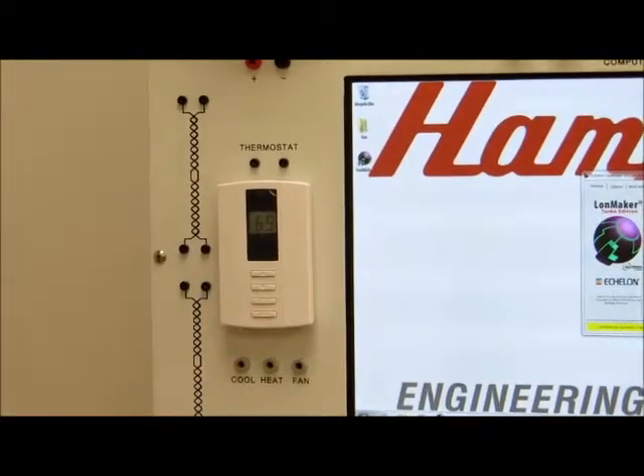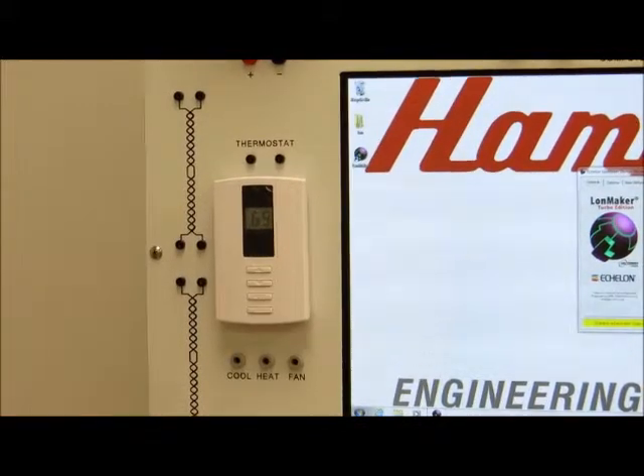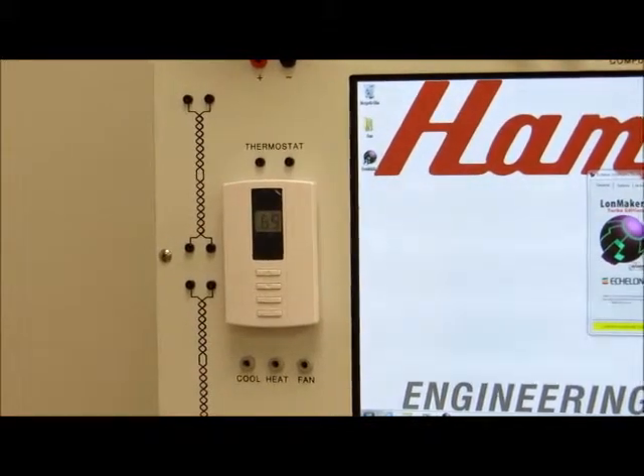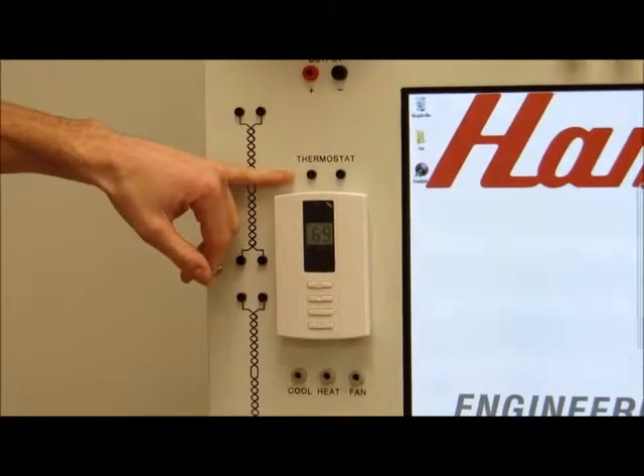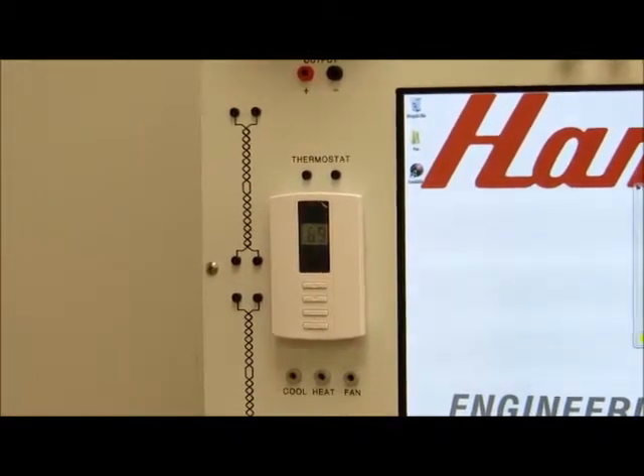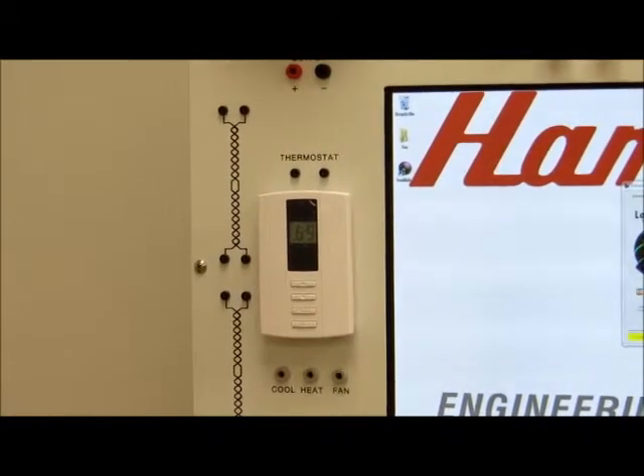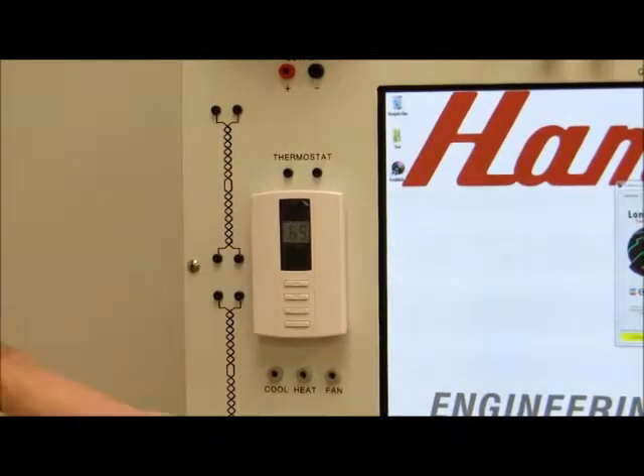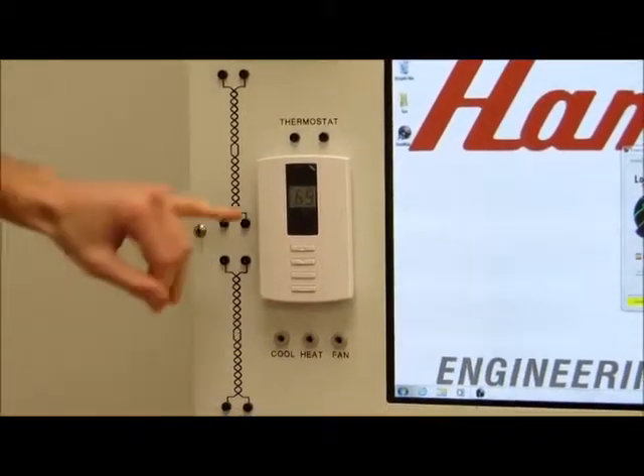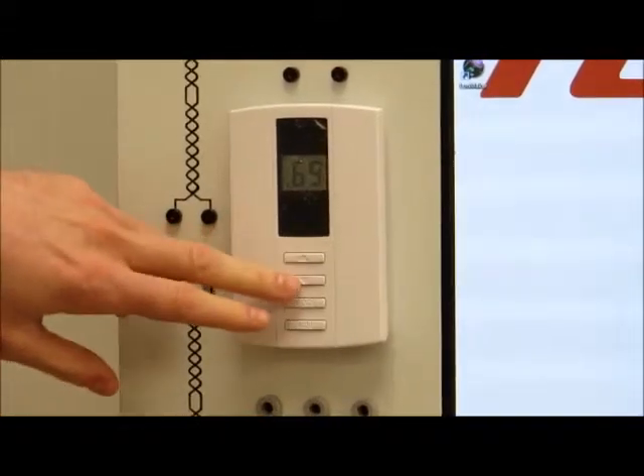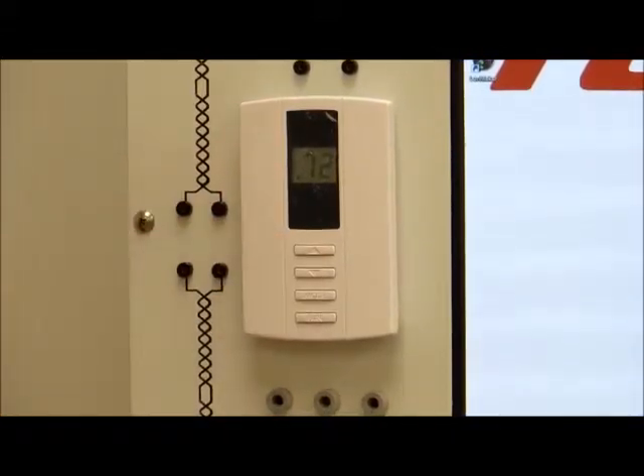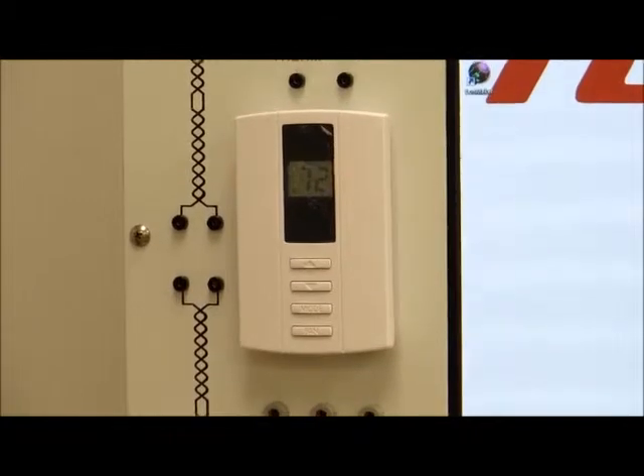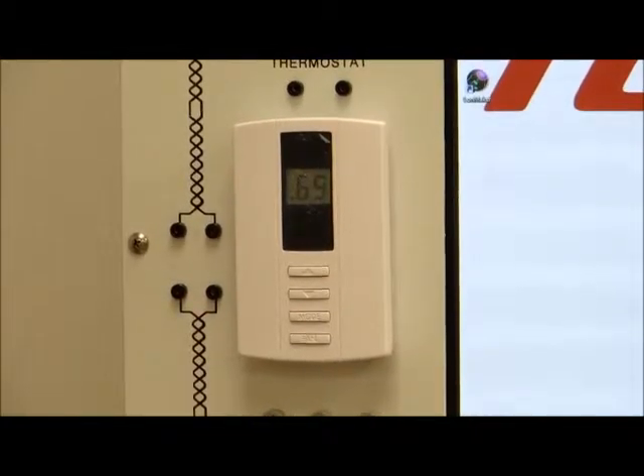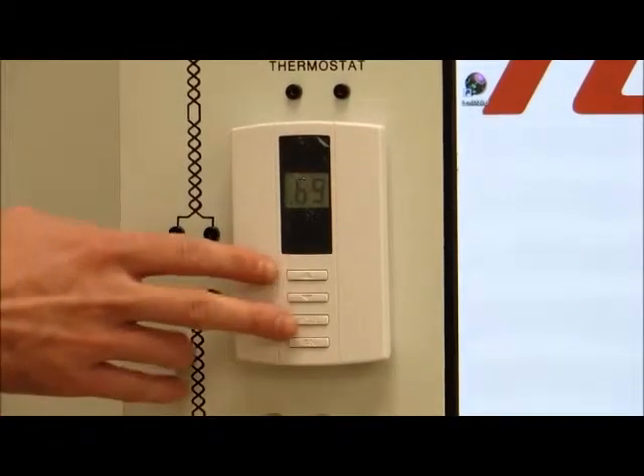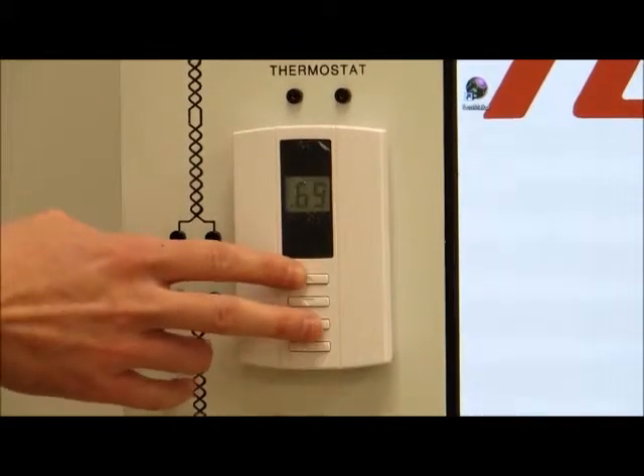Alright, the next device is the thermostat. The thermostat does talk over the network with LonMaker. The network jacks are right above it. The thermostat has 2 modes, cool and heat, and the fan output as seen below. The room temperature is displayed on the thermostat. The up and down buttons will change your set point of the thermostat to bring it into cool mode or heat mode. And the service pin for this device is by pressing the up button and the mode button together.